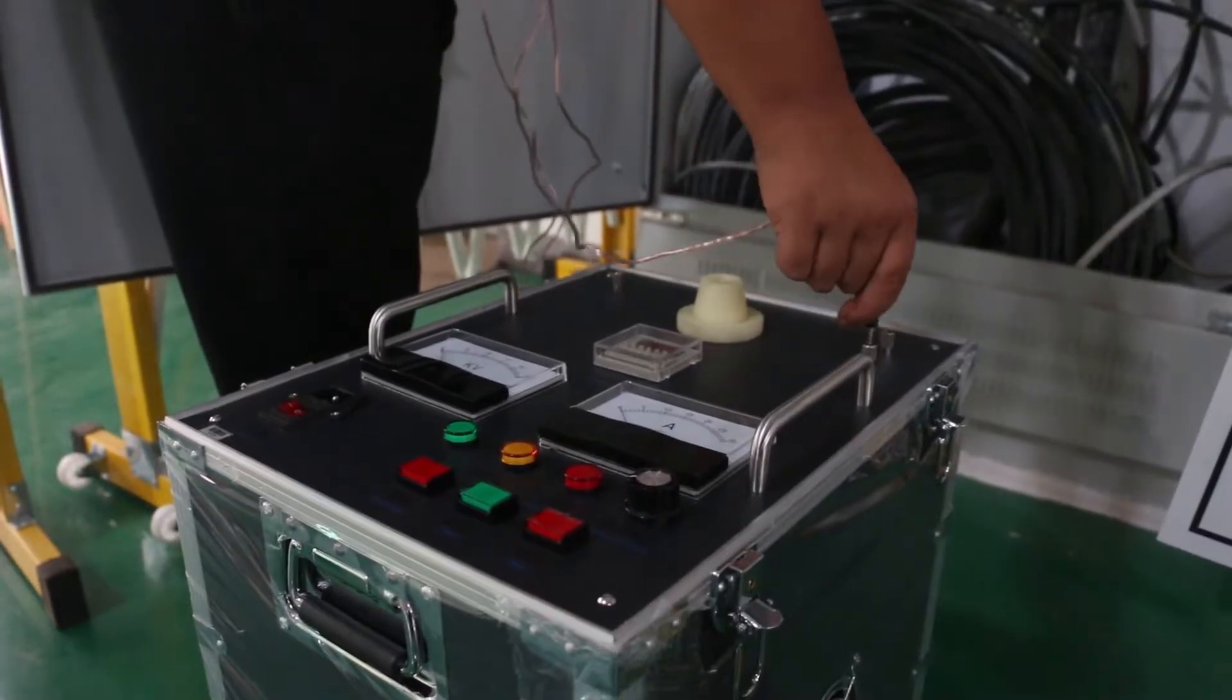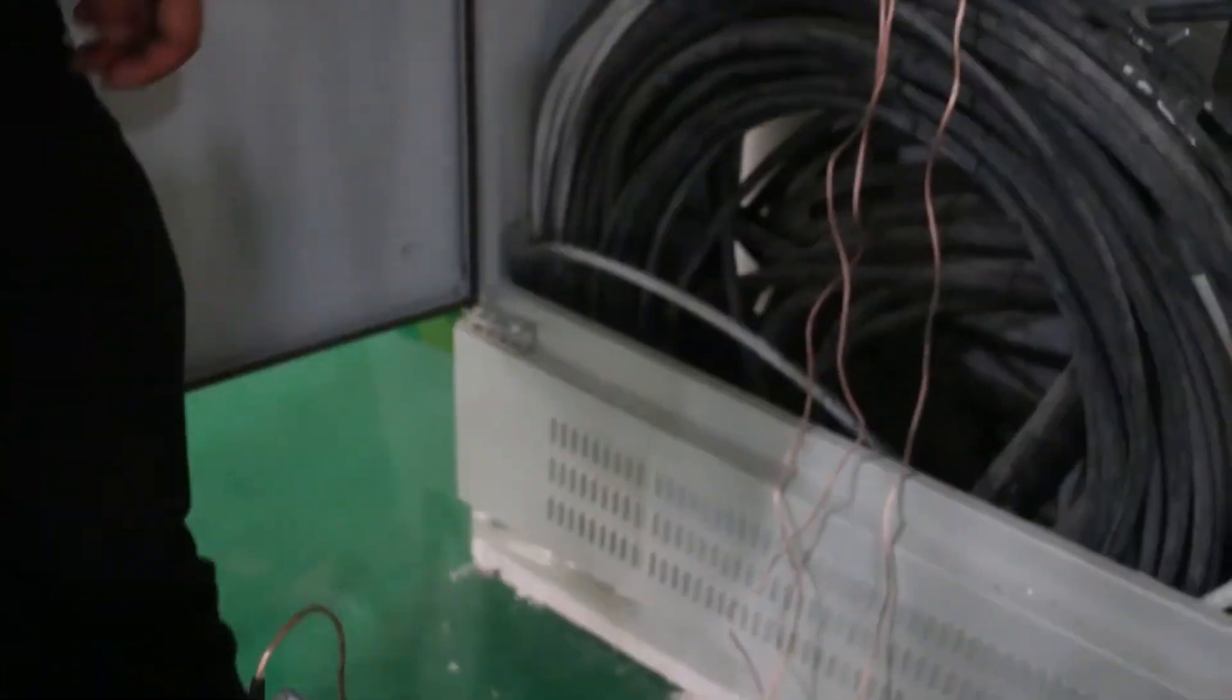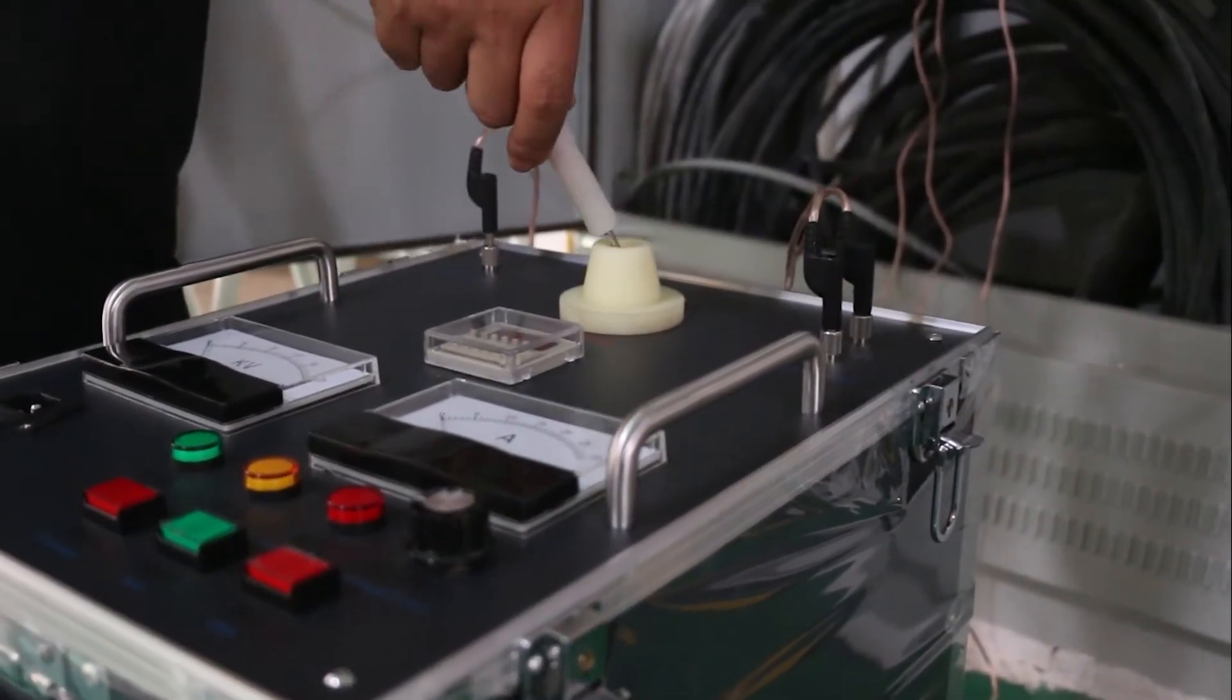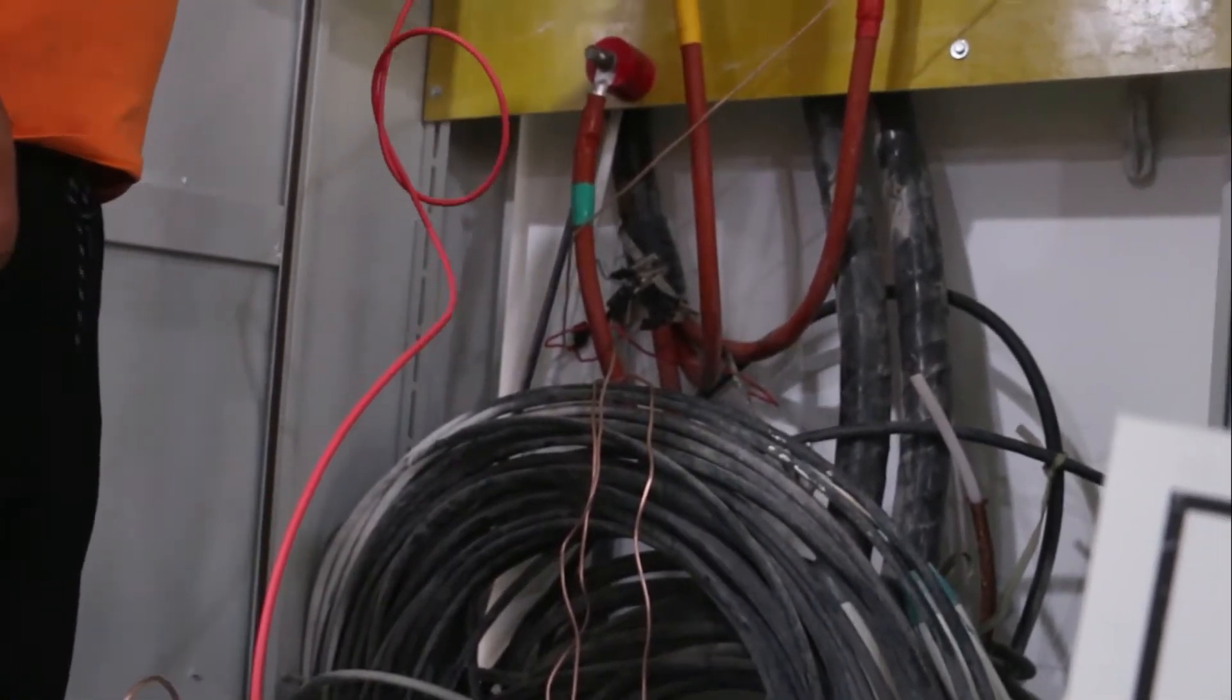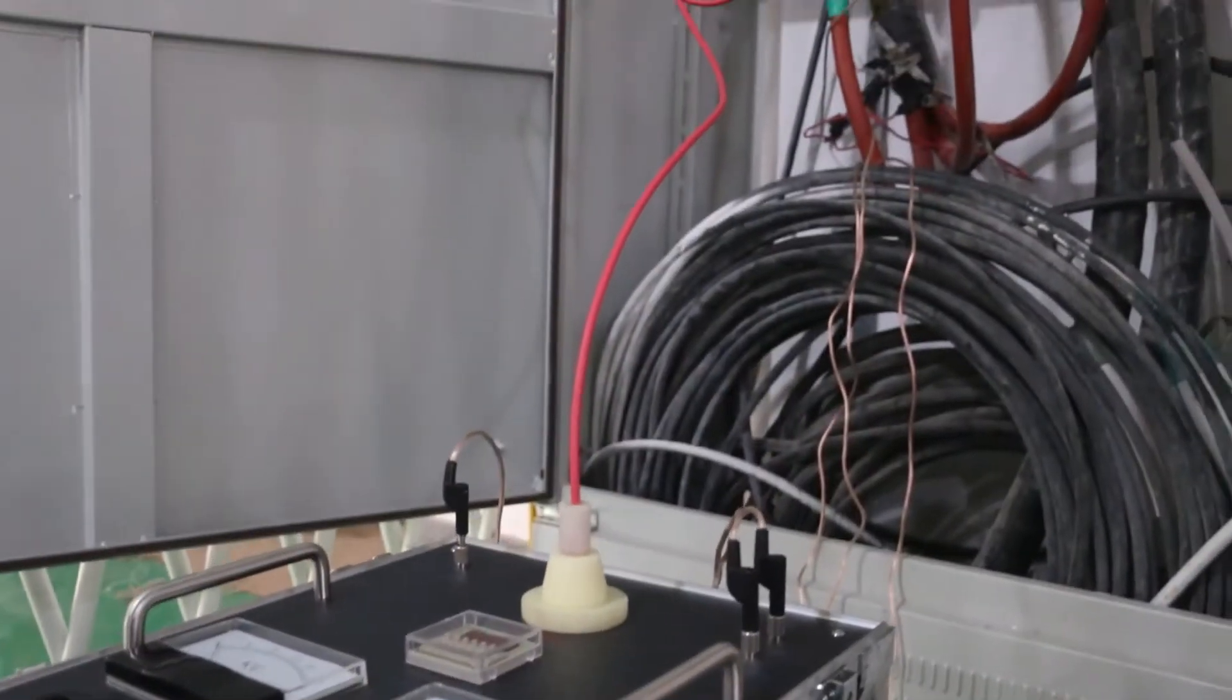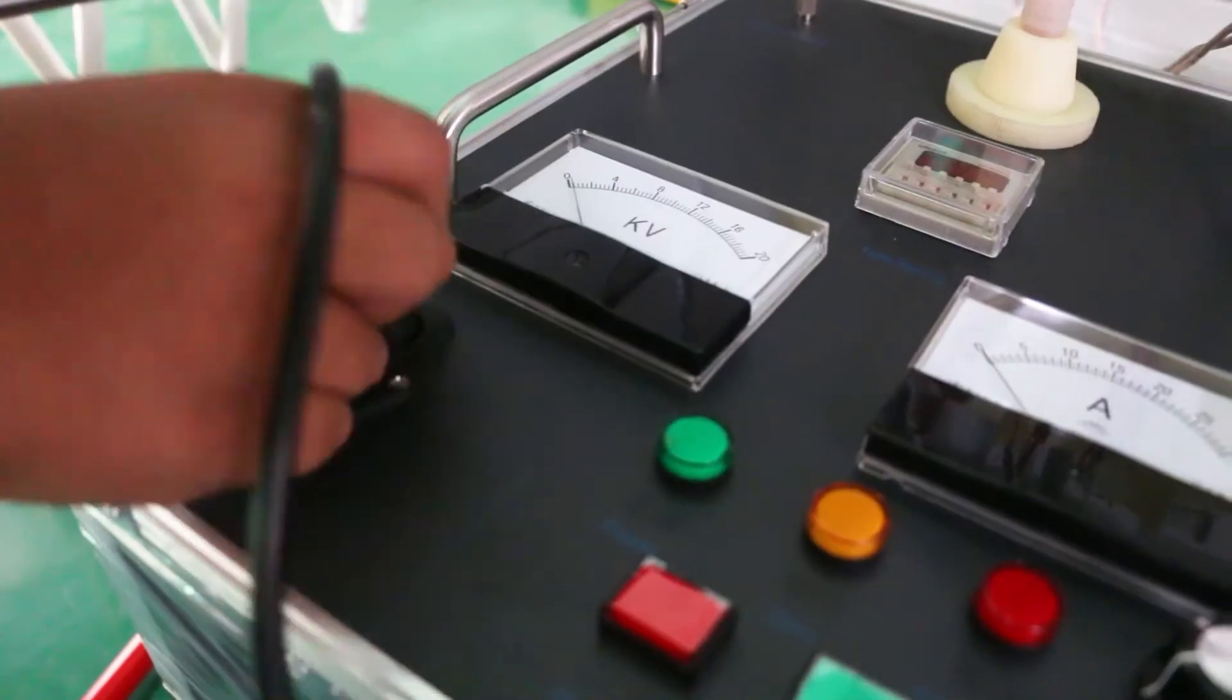First, connect high-voltage ground, sampling ground, and safety ground to earth well. Note that sampling ground must be connected to copper tape of cable. High-voltage output test lead connects with core of cable. Discharging rod should connect to earth well.